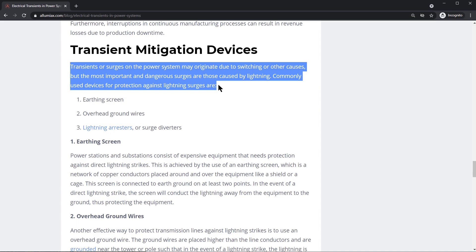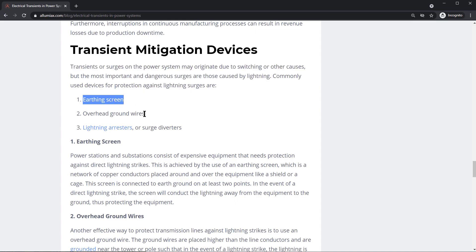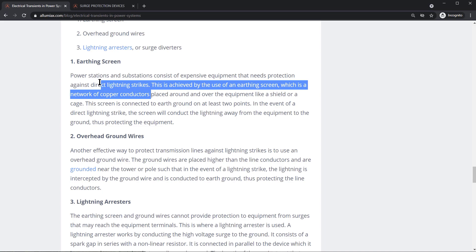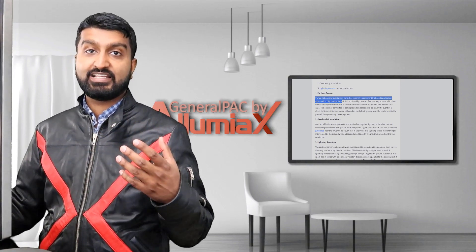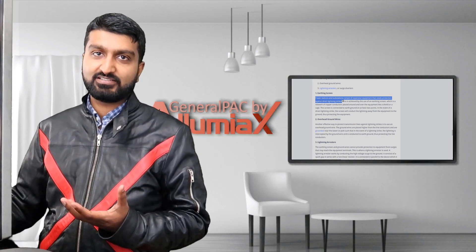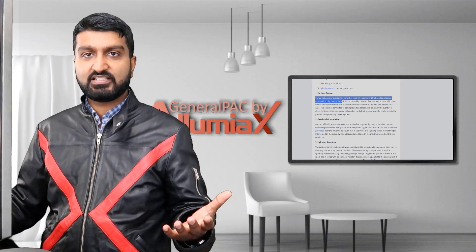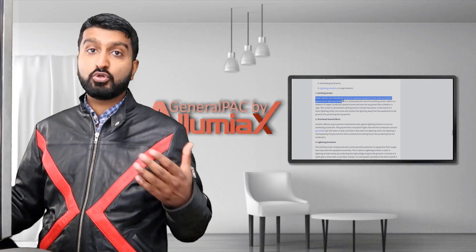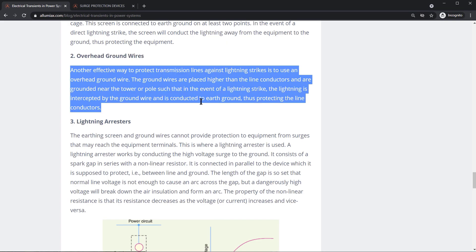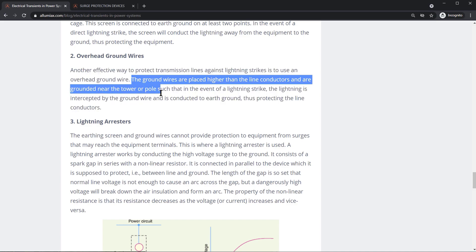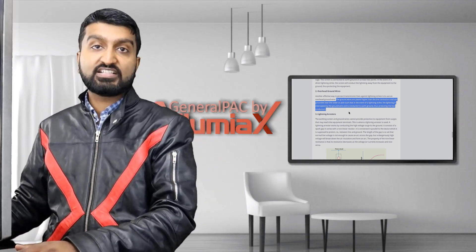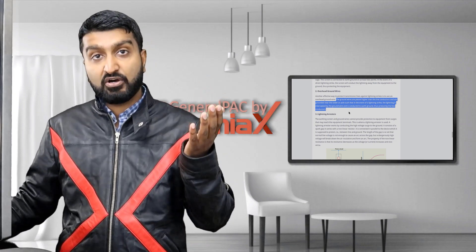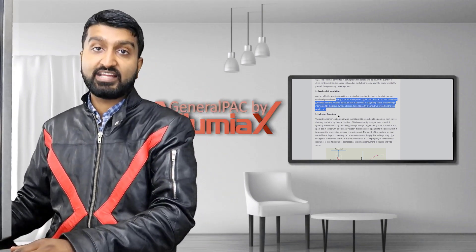Commonly used devices for protection against lightning surges are earth screens, overhead ground wires, and lightning arrestors. Substations represent millions of dollars of investment, and if that investment fails due to lightning — which can be very probable depending on the environment — that is a huge risk. Overhead ground wires protect transmission lines against lightning strikes by providing a wire that the lightning hits first, rather than the phase conductors.